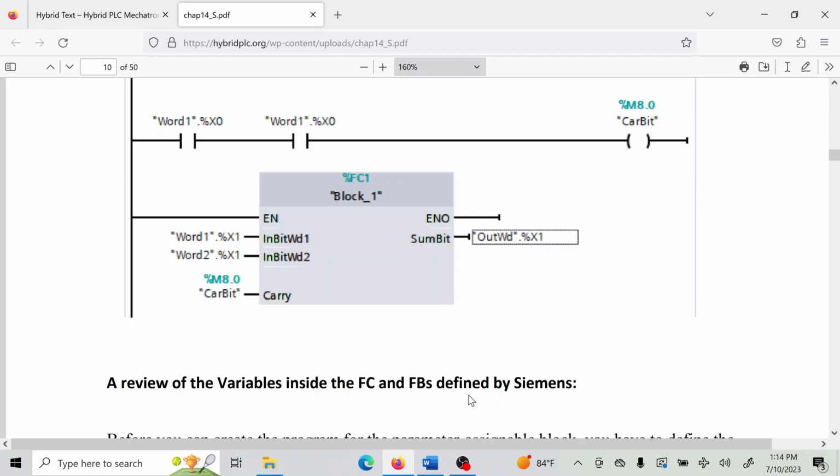If you want to write large programs with variables and you don't want to use your M table for them, what would be a logical place to write those programs? Well, it'd be in an FB. In the FB, you would have these static variables that are assigned by name, and they can either be for just that program or they can be accessed by other programs as well.